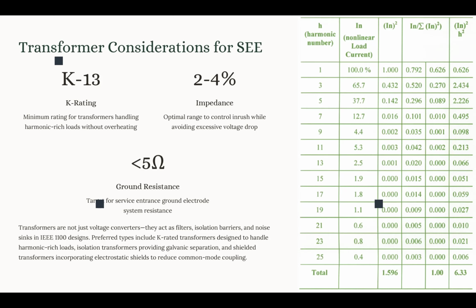Now, a non-K rated transformer will overheat and fail when we talk about harmonic-rich conditions. Okay, now the transformer also has an impedance rating, and the recommended range for the transformer used with sensitive electronic equipment is 2 to 4% impedance, and it's for power frequency impedance. Okay, so the lowest impedance the transformer should have is 2%. If we go lower than 2%, the transformer basically allows high inrush current, which means a lot of tripping and voltage dips for the other loads that are connected to that transformer.